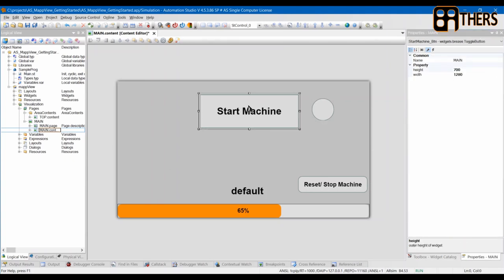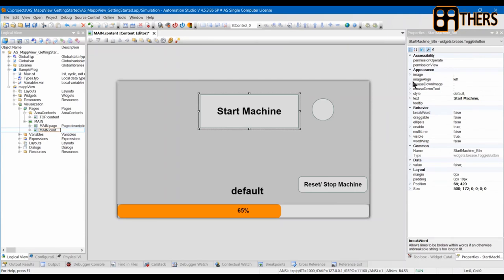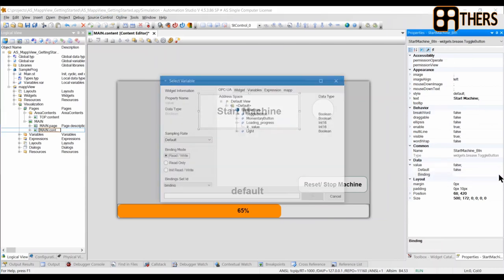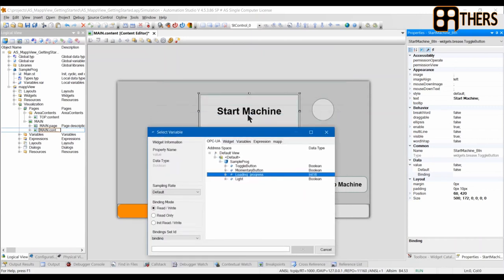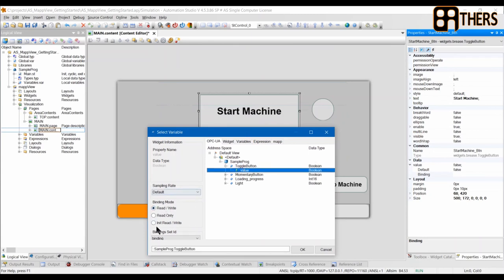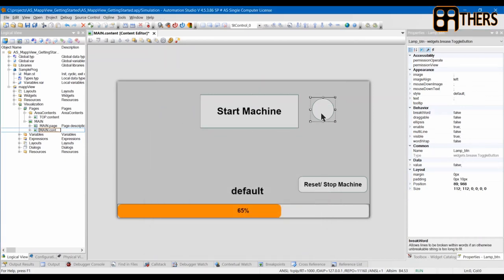Now we're going to map the widgets to our values in the OPC UA. Click to hide information we don't need, go to Data and Bindings, click the three dots. You can see the sample project with all the data given in OPC UA. My 'start machine' will map to my toggle button. Note the Binding Set ID — this is the binding added in the Configuration View. The binding mode options are: Read and Write, Read Only, and Init Read and Write (reads once at startup).